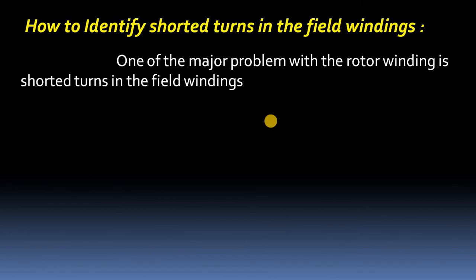Shorted turns exist in the rotor winding because of aging of the machine, thermal stresses, or on-off cycles — meaning we give supply to the rotor winding when we need the generator voltage and turn off the DC supply when we don't. Because of these on-off cycles, shorted turns will exist in the field poles.